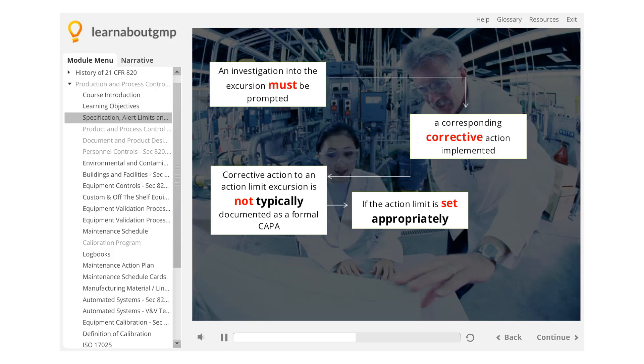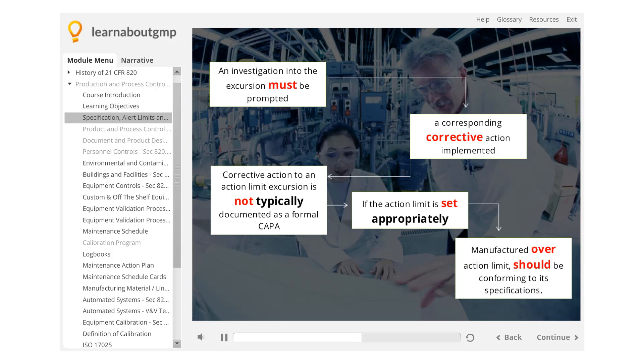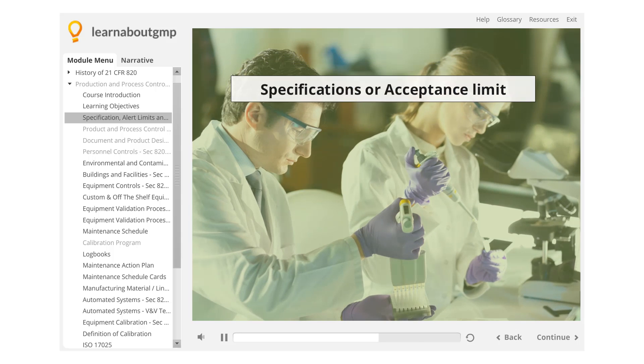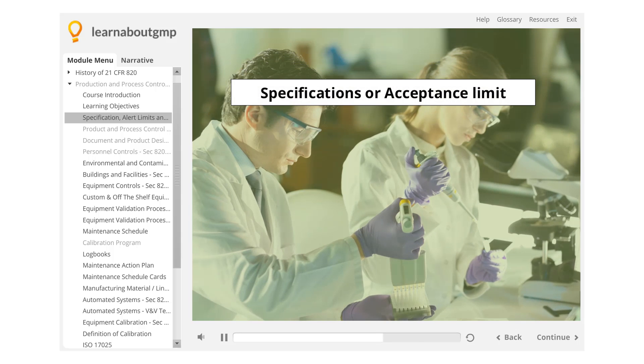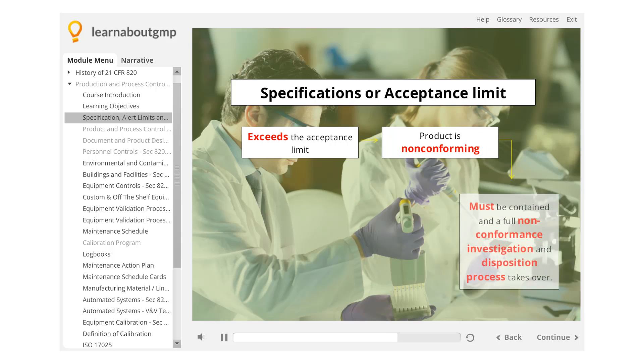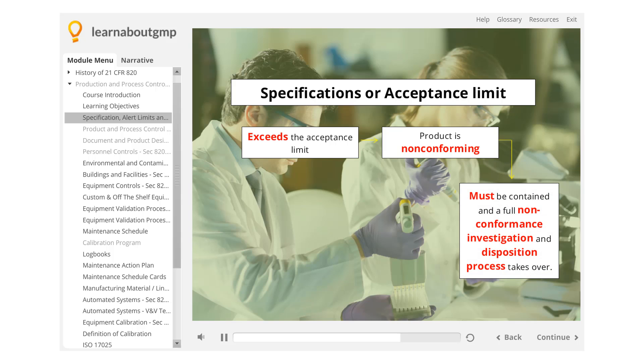If the action limit is set appropriately, product or processes which were manufactured over the action level should still be capable of meeting their intended requirements and therefore should be conforming to specifications. The last level of action is the Specifications or Acceptance Limit. If the product exceeds the acceptance limit or specification requirements, then the product is non-conforming and must be contained, and a full non-conformance investigation and disposition process takes over.